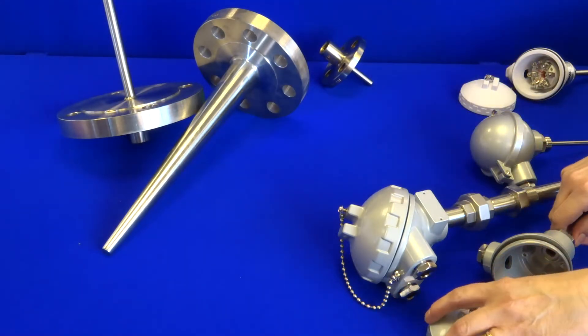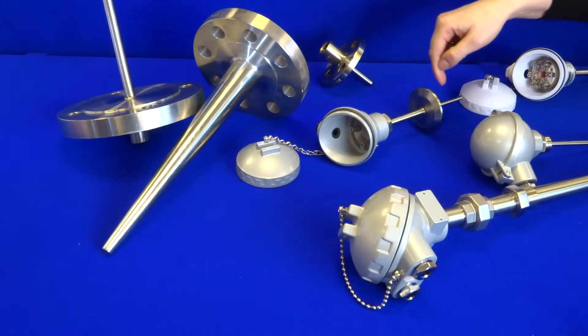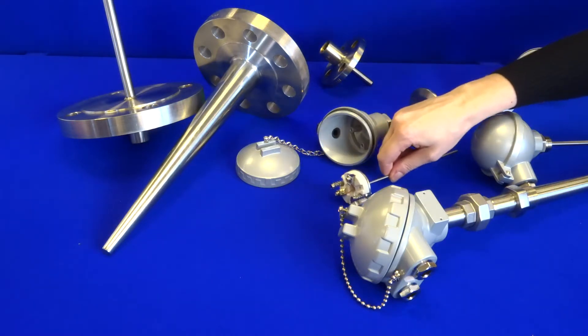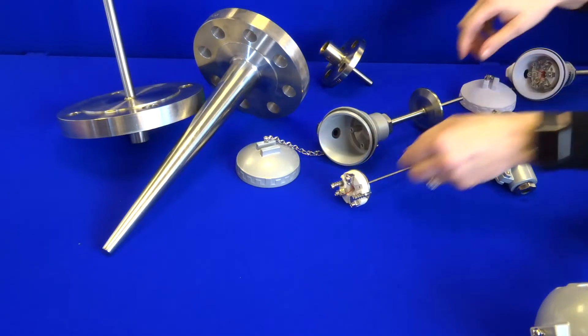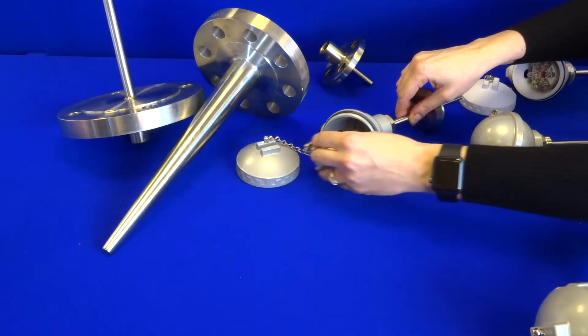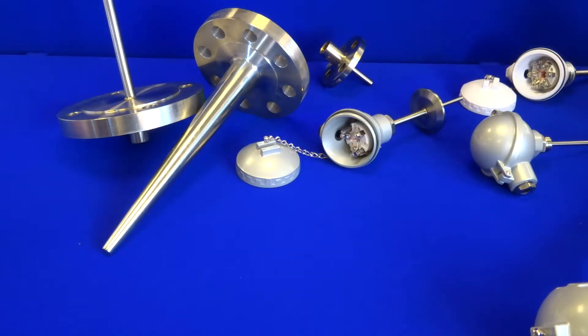Next we have the medium-duty range, which consists of a fabricated thermowell and a separate temperature sensor insert. The insert is removable and replaceable — for example, this can be removed for regular calibrations without disturbing the process, and it's ideal when downtime is critical.